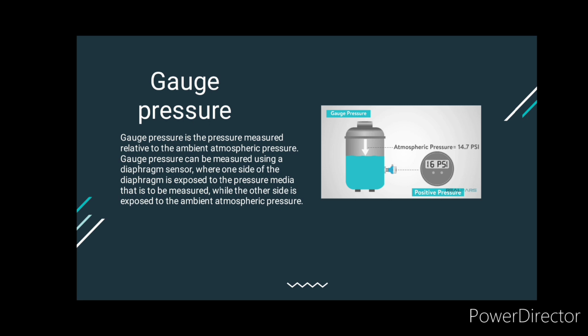Gauge pressure. Gauge pressure is the pressure measured relative to the ambient atmospheric pressure. Gauge pressure can be measured using a diaphragm sensor, where one side of the diaphragm is exposed to the pressure media that is to be measured, while the other side is exposed to the ambient atmospheric pressure.